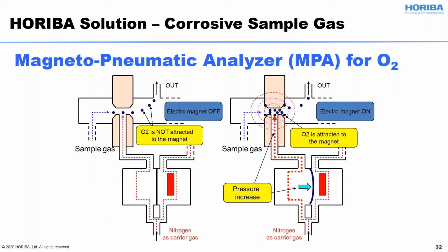Another thing is the O2 analysis. This is a simple schematic to show you how it works. The sample gas flows like this from inside to out, right? And oxygen has the feature of being attracted by a magnet. So while the magnet is off, O2 is not attracted to the magnet, so the sample just flows from the inlet to the outlet, right? When an electromagnet is on, O2 starts being attracted to the magnet right here, and this causes some pressure increase inside the chamber right here, and this pressure bends the membrane, and the degree of bending of the micromembrane is related to the O2 concentration.